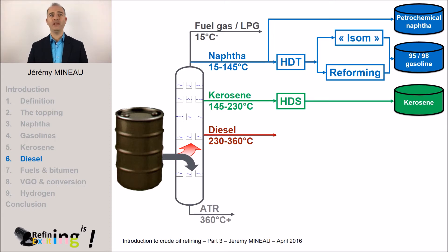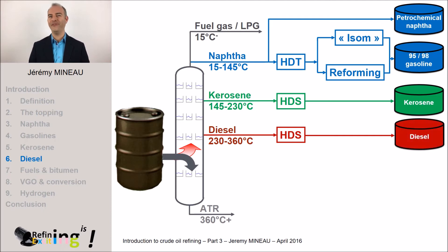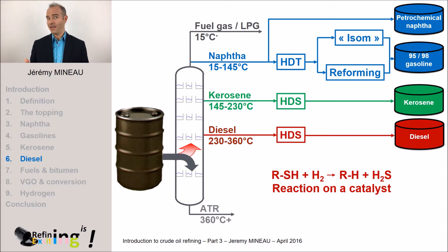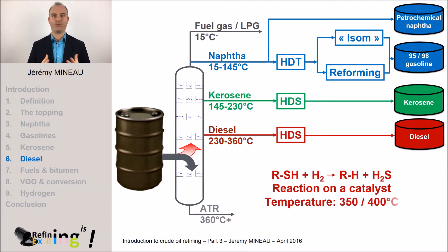Generally speaking, in the refinery, we can find a diesel hydrotreater to remove the sulfur from the diesel fuel with the help of hydrogen. The catalyst is always the same, but the operating conditions are more severe than for a naphtha hydrotreater. Why? Because the molecules are more complex and more difficult to treat. The temperatures can go up to 400 degrees and the pressures can reach 40 to 90 bars.